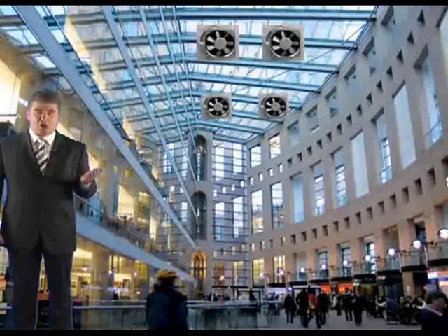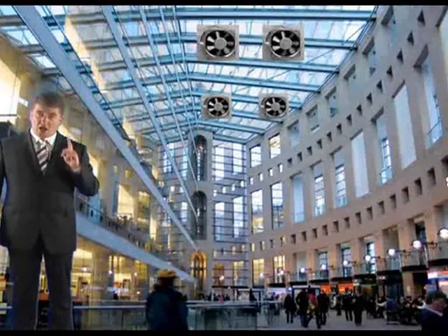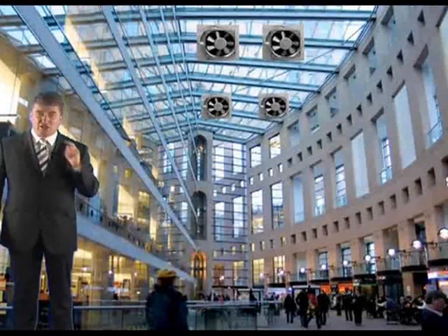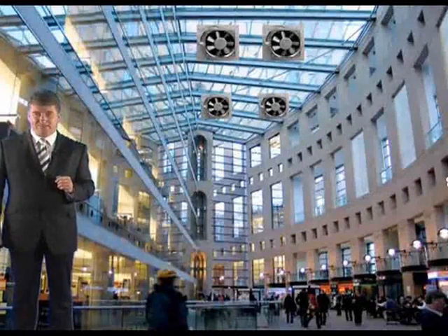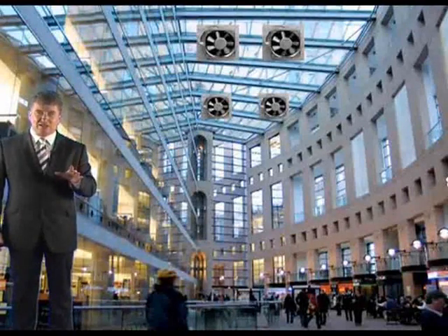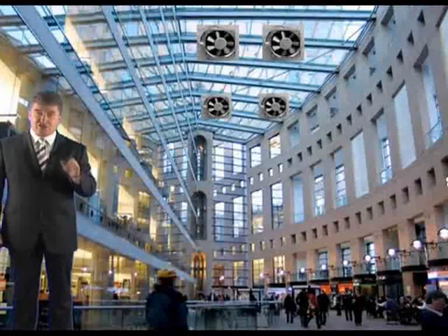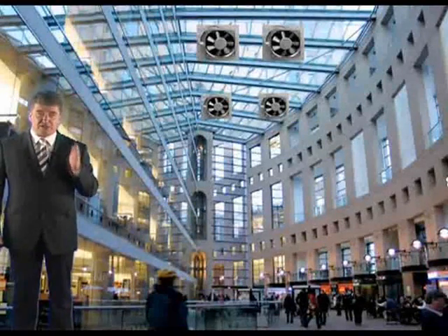People escaping from a shop into a mall will still need to travel along the mall before exiting to a true place of safety. And it follows that the mall constitutes an additional stage to the escape route, which needs to be protected from the effects of fire and smoke. Now, if you're not going to protect it with loads of compartmentation, which they don't want to do, they don't want loads of compartment walls and compartment floors, they want an open feel. Well, if you're not going to use compartmentation, you need another method, and that's where the smoke, heat and exhaust ventilation system comes in.